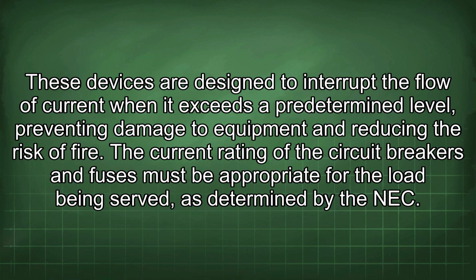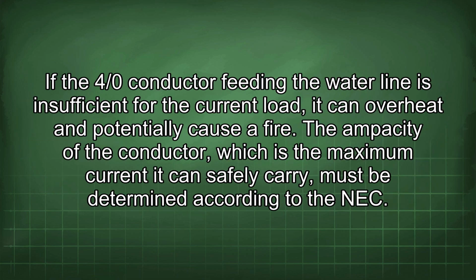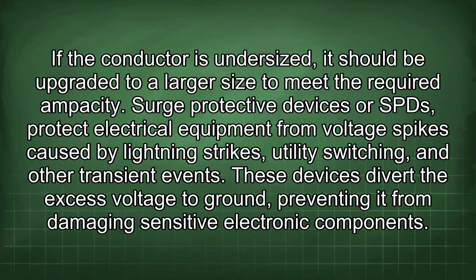The current rating of the circuit breakers and fuses must be appropriate for the load being served, as determined by the NEC. If the 4/0 conductor feeding the water line is insufficient for the current load, it can overheat and potentially cause a fire. The ampacity of the conductor, which is the maximum current it can safely carry, must be determined according to the NEC. If the conductor is undersized, it should be upgraded to a larger size to meet the required ampacity.